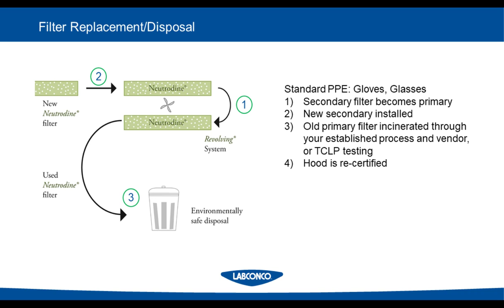Once the fan has been removed and put back in place and the filters have been changed and rotated, you need to recertify that hood. Filtered hoods, just like ducted hoods and ductless hoods, should be annually recertified by a third-party independent company with no stake in the game. They come in, read face velocity, and make sure you're running a safe hood at the sash operating height previously dictated.